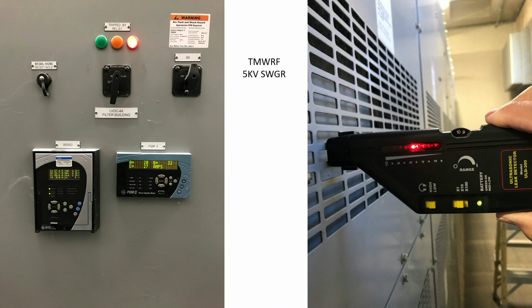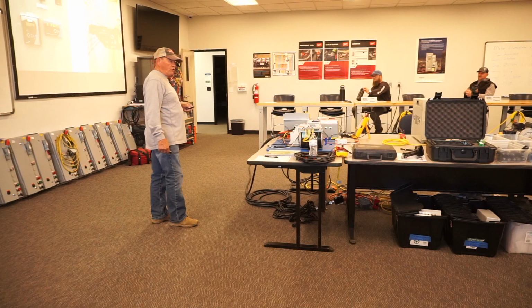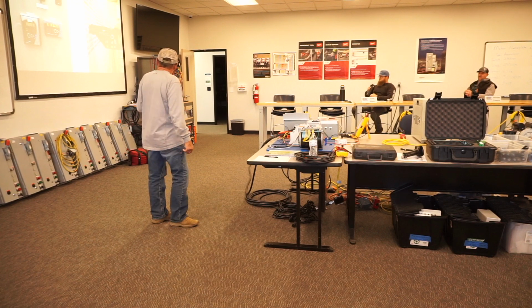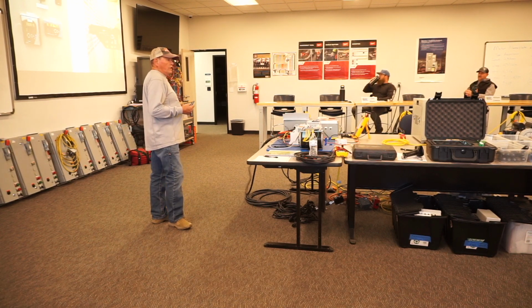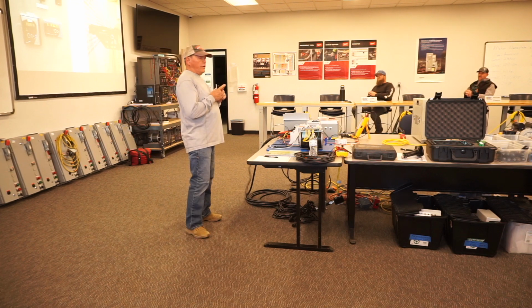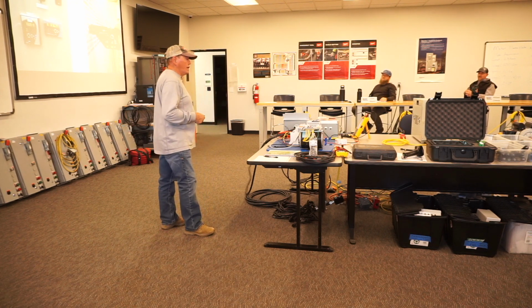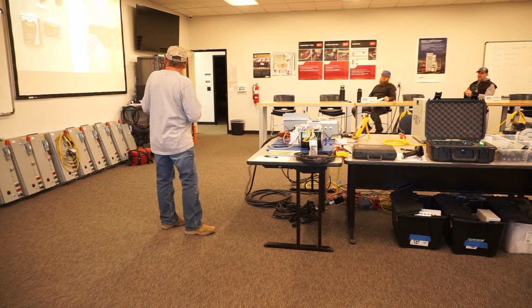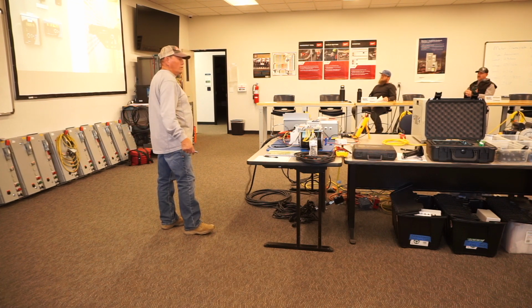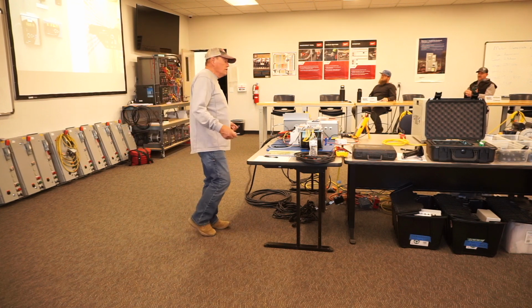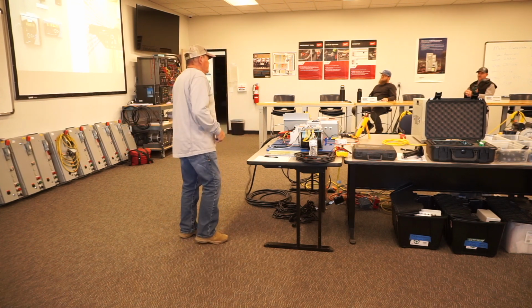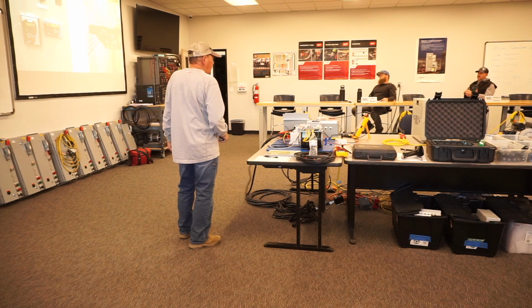Non-invasive. And if you got breakers that are tripping, nuisance breaker trippings, it's a great test for that, because when contacts get dirty and pitted, they'll buzz. They'll buzz at 60 hertz. We call it microscopic arcs and sparks that happen inside those contacts, and that puts out ultrasonic sound. And so I use that to test for loose terminations before they generate heat and create a problem. Just a nice test tool to carry around in your ditty bag.